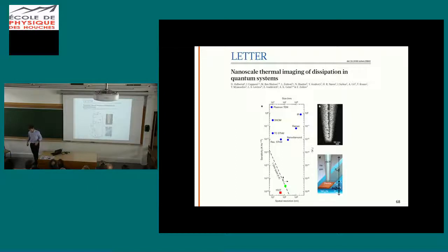Those are two excellent questions and actually kind of related. So how do we get the thermal contact? Of course, if you're in vacuum, as we like to be, there is no thermal contact between the sample and your SQUID. So what you have to do is introduce some exchange gas. All of these thermal measurements are enabled by exchange gas, and you have to introduce the right amount because basically you need a stronger thermal contact to the device that you're measuring than to the environment, which is essentially coupled through the SQUID tip. But that's actually not so complex to do because the leads are superconducting, so they're very well isolating, and this is a very narrow quartz tube, which is also very isolating. So there's quite a big parameter space where you can tune the thermal coupling to where you want.